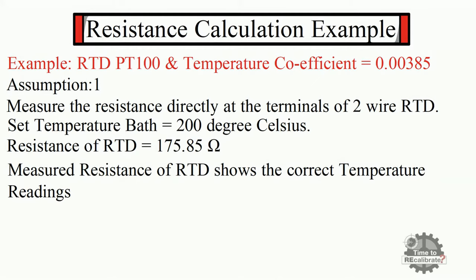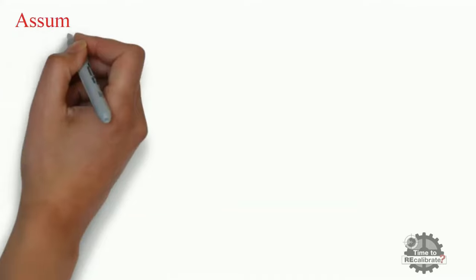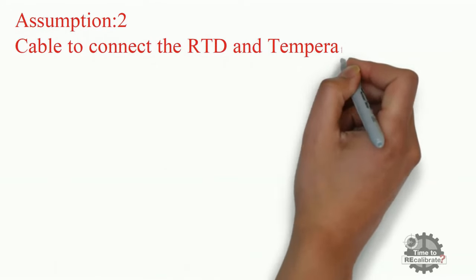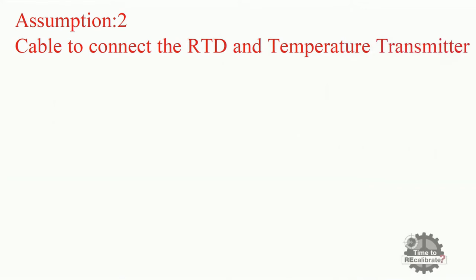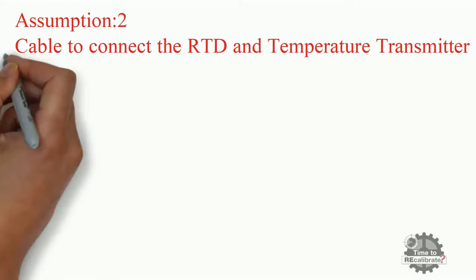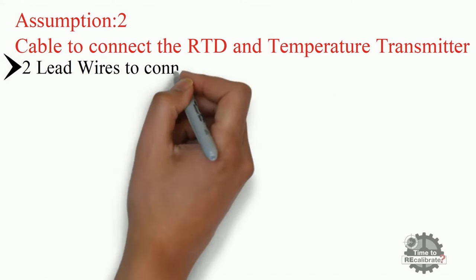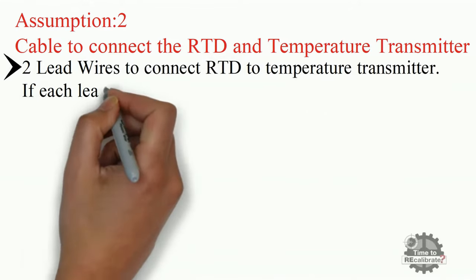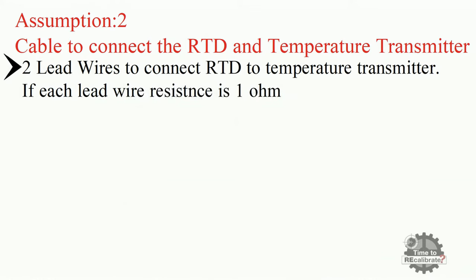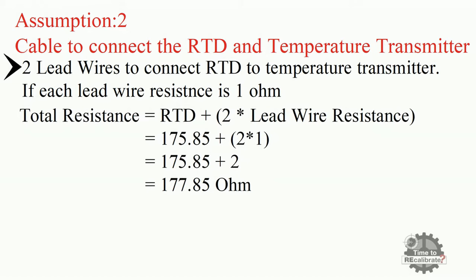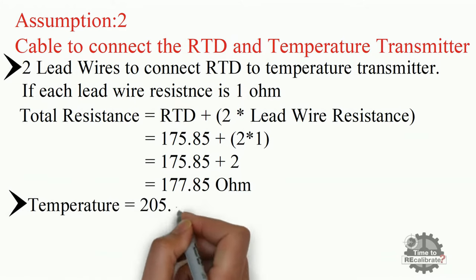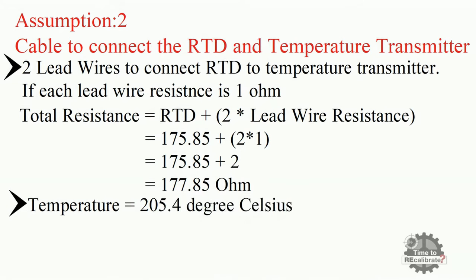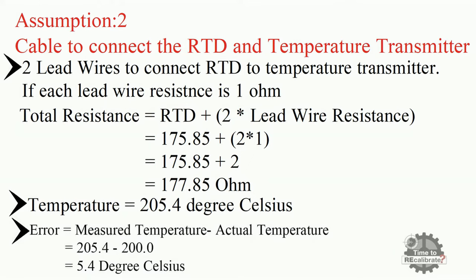Let's take one more example to understand lead wire resistance in detail. In industry applications, we use a cable to connect the RTD to the temperature transmitter. This cable resistance is known as lead wire resistance and will add to the total resistance. For example, if we use two lead wires each with 1 ohm resistance, and put all these values into the equation, we get 177.85 ohms. The temperature according to this total resistance value is 205.4 degrees Celsius, which is incorrect. The error is 5.4 degrees Celsius — the lead resistance introduced a measurement error of 5.4 degrees Celsius.